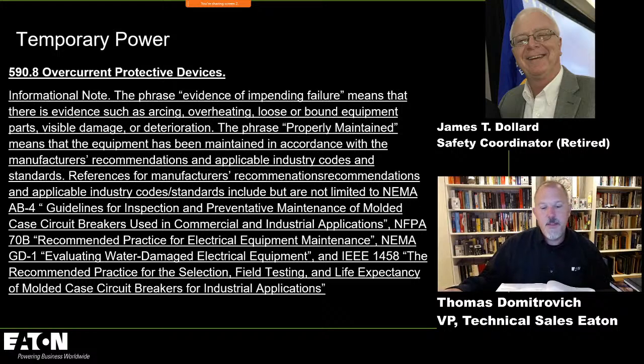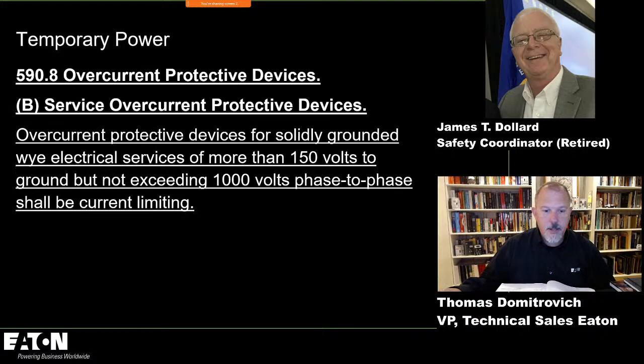Yep. And then I think if you go to the next slide is where you'll see the current limiting requirement. The what? Oh yeah. That's right. That was solidly grounded, not exceeding 1,000 volts phase-to-phase shall be current limiting. Yeah, and that's a really good example of a safety-driven revision to the NEC.